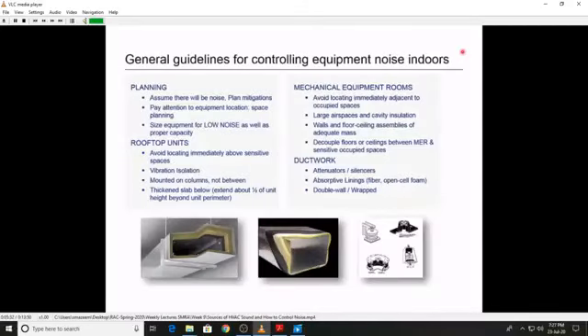But what are some of the things you can do to reduce indoor noise from HVAC systems? Well, number one is, if you have the opportunity, planning is your best friend. You must assume that there will be noise, and you have to plan mitigations in advance. You have to pay attention to the equipment location in your space planning, and you need to size your equipment for low noise as well as proper capacity. Once installed, a low noise unit will do you a lot more good than trying to retrofit a noisy unit.